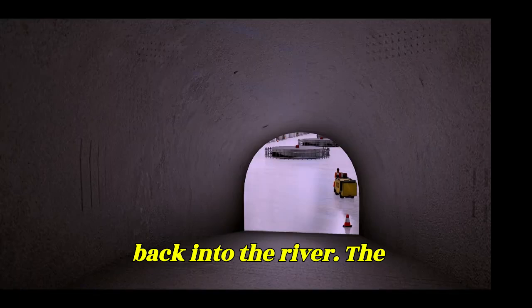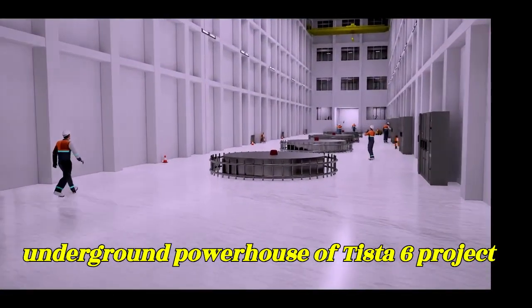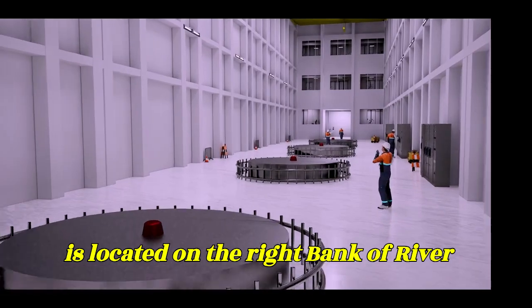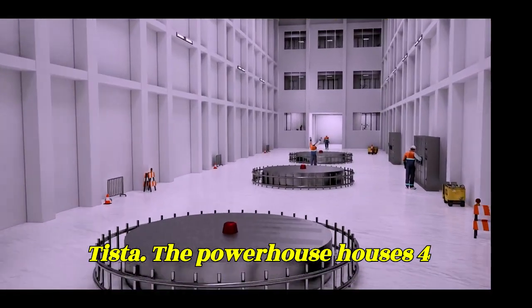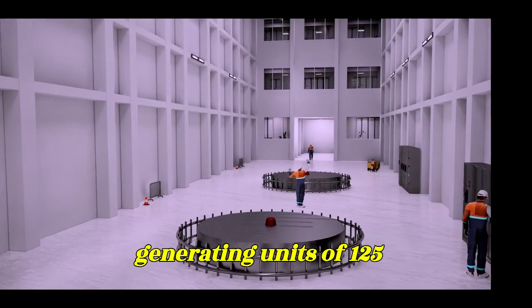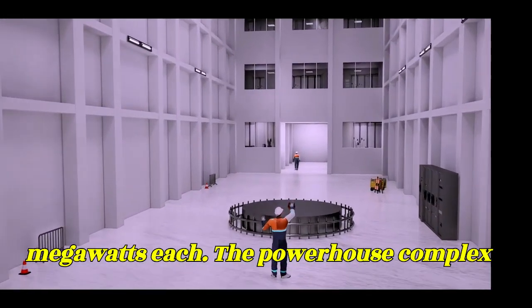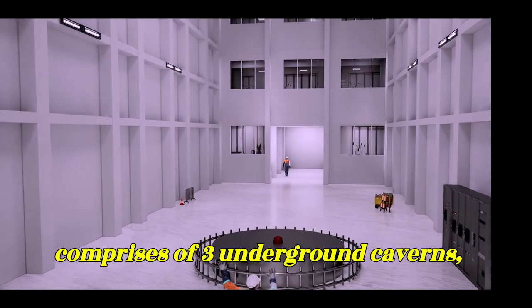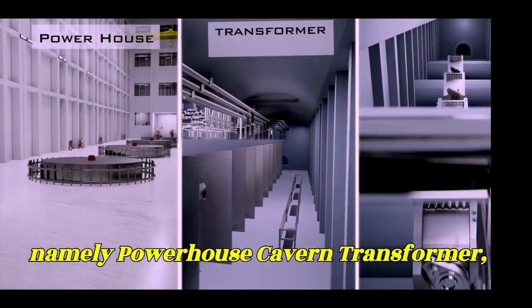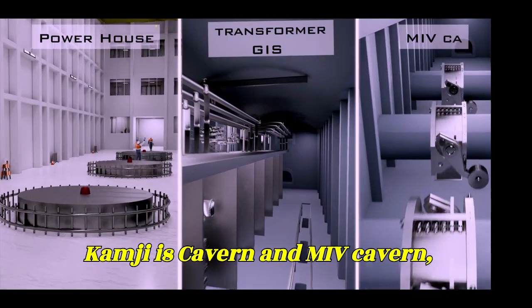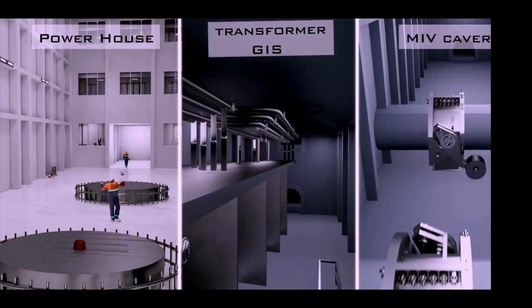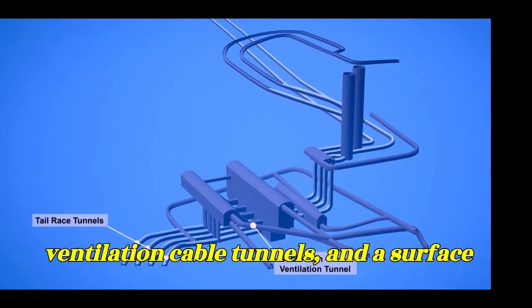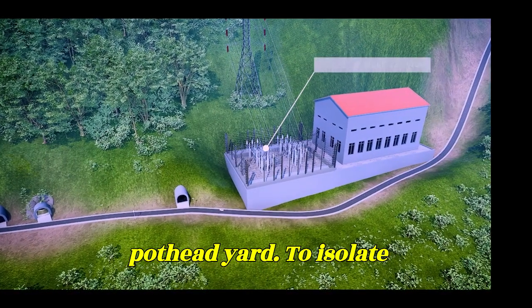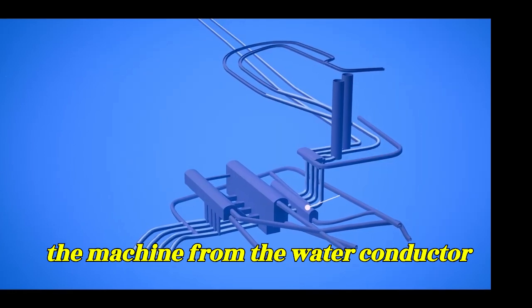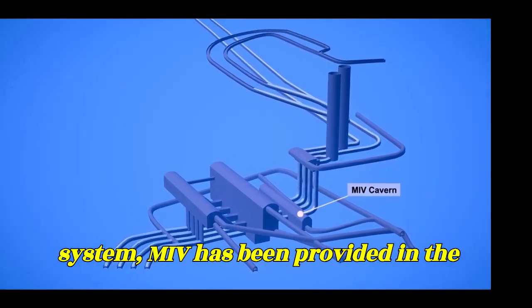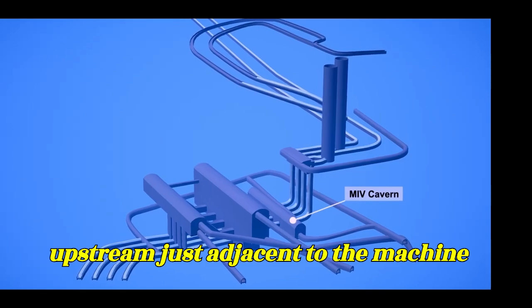The underground powerhouse of Teesta 6 project is located on the right bank of river Teesta. The powerhouse houses 4 generating units of 125 megawatts each. The powerhouse complex comprises 3 underground caverns, namely Powerhouse Cavern, Transformer GIS Cavern and MIV Cavern, tail race tunnels, main access and ventilation cable tunnels, and a surface pot head yard. To isolate the machine from the water conductor system, MIV has been provided in the upstream just adjacent to the machine hall.